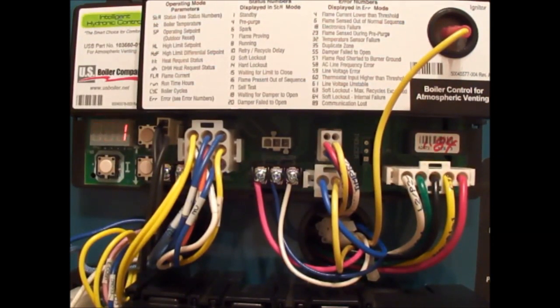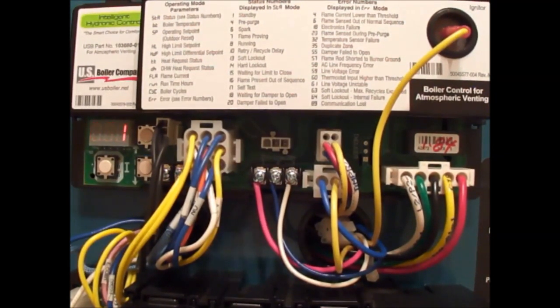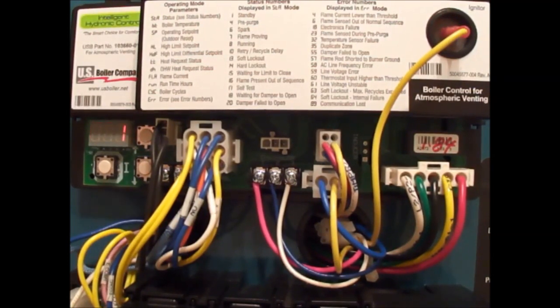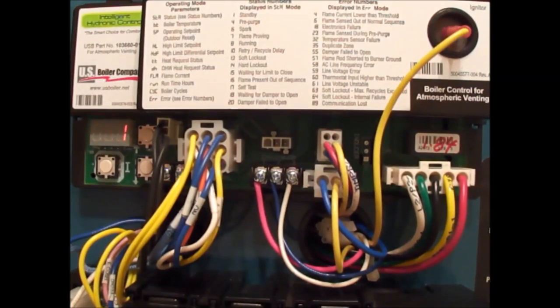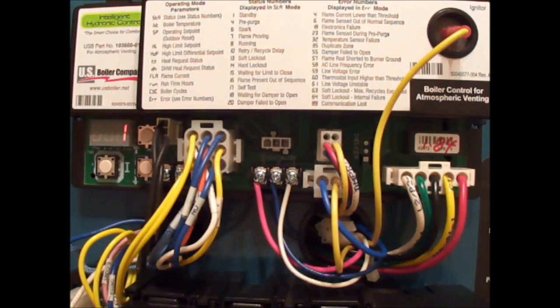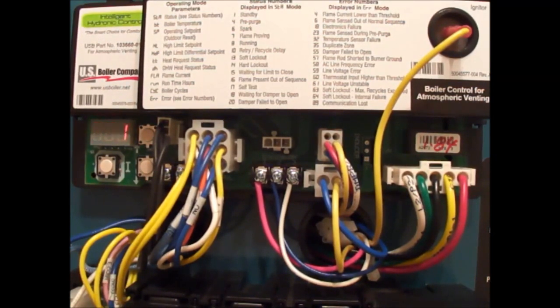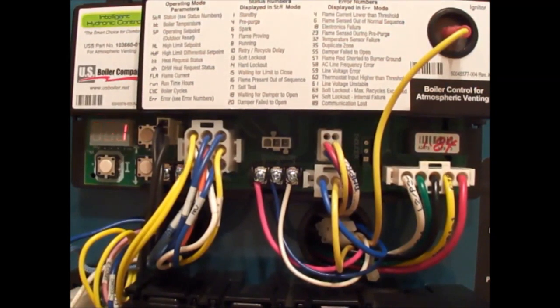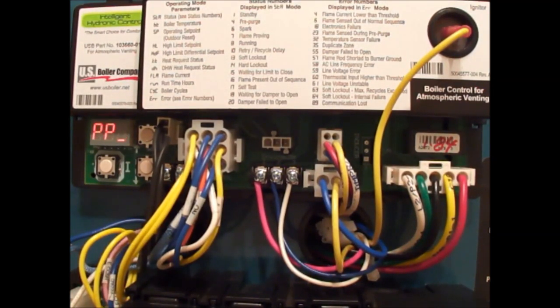The next one we have is pre-purge. Pre-purge is a setting where the pump comes on first and we use residual heat first. This is a nice feature because we're using the heat in the boiler before we fire the boiler. If the boiler has more than 140 degrees water temperature and we get a call for heat, we do not fire the boiler. This is a new code that came about September 1st of 2012.